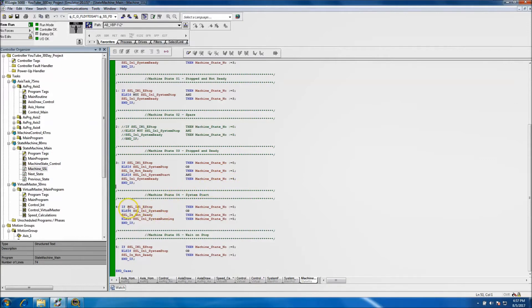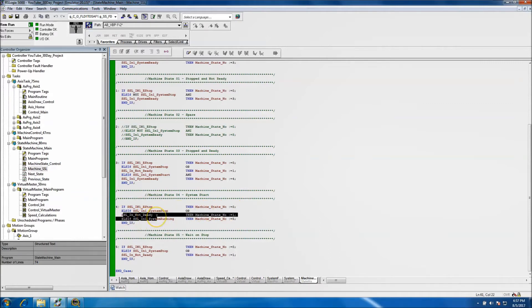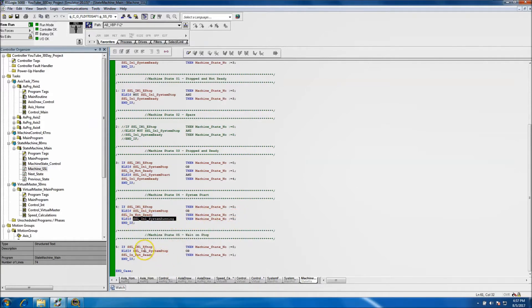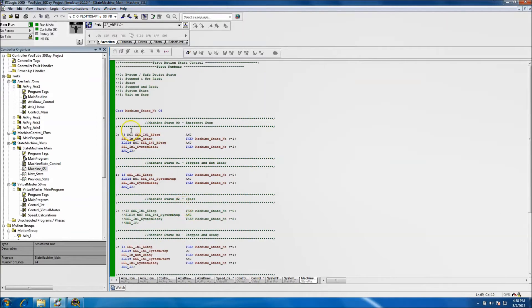In state 4, if the E-stop hits it goes to 0. If stop is pressed or the system is not ready, it goes to 1. If the system is running, it goes to state 5. In state 5, all it's doing is waiting for the stop — either an E-stop or a stop button can stop it.